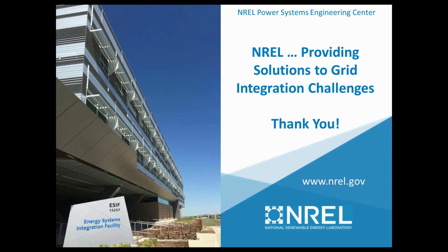Maybe this is something that we take offline and try to do a little bit more in-depth study on, because one of the big challenges is that there are potentially solutions for overvoltages and for this unintentional islanding that require very expensive solutions. So coming up with some lower cost solutions for addressing some of these issues would probably be critical to look at. But we could probably reduce that to a subset here, looking at these overvoltages on the single line to ground fault and what to do about direct transfer trip costs.